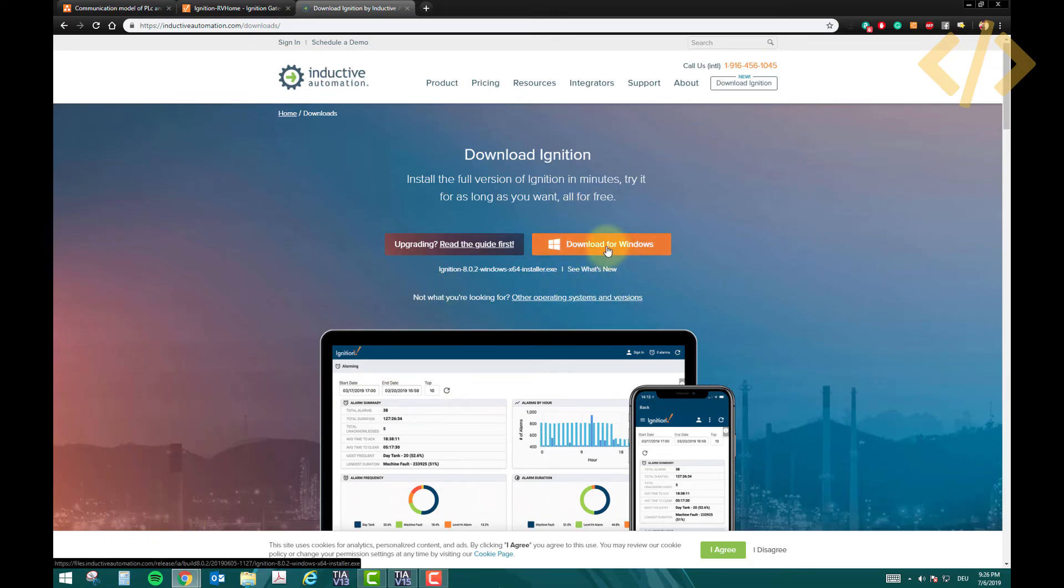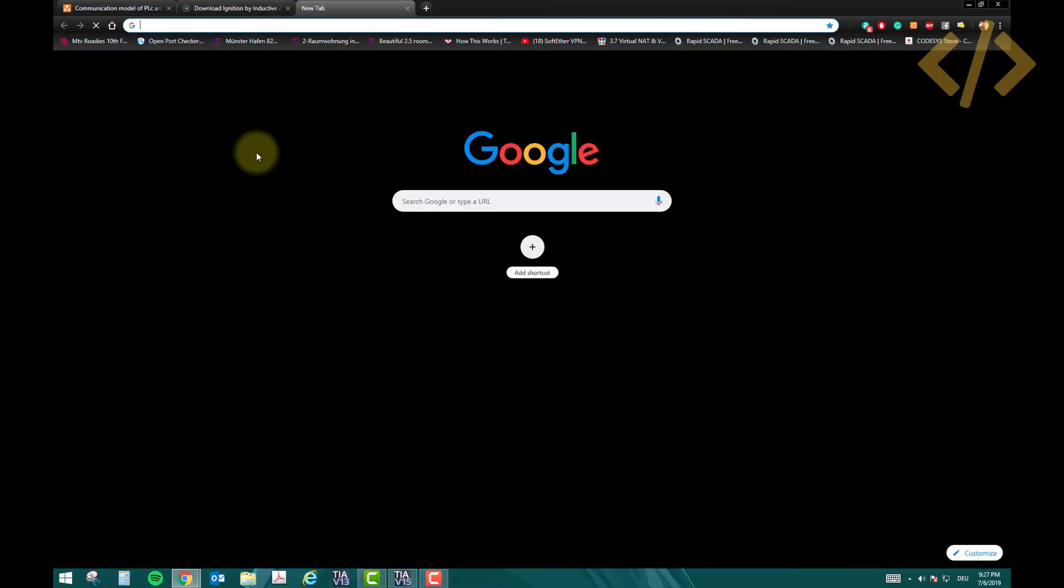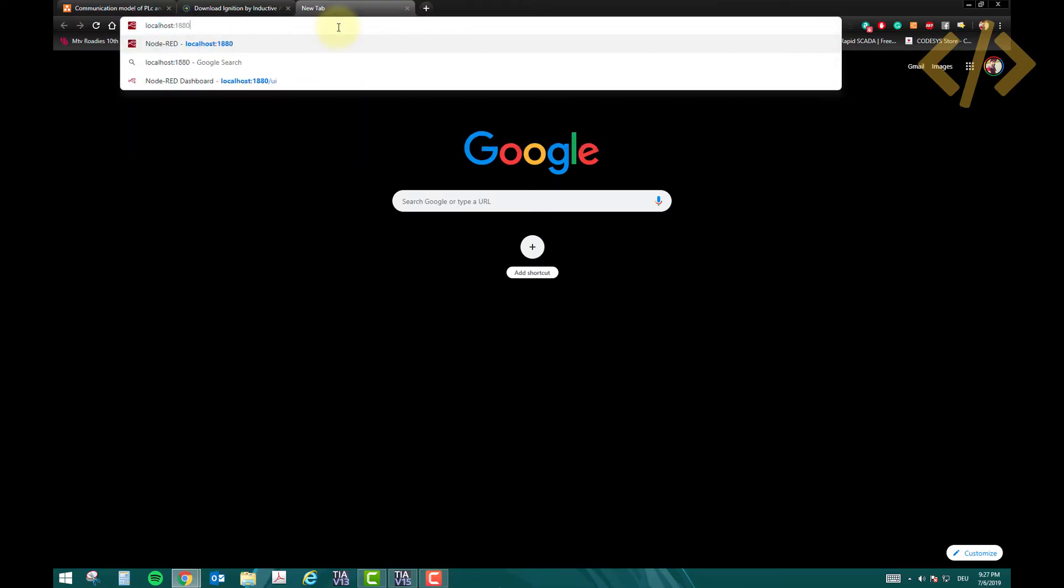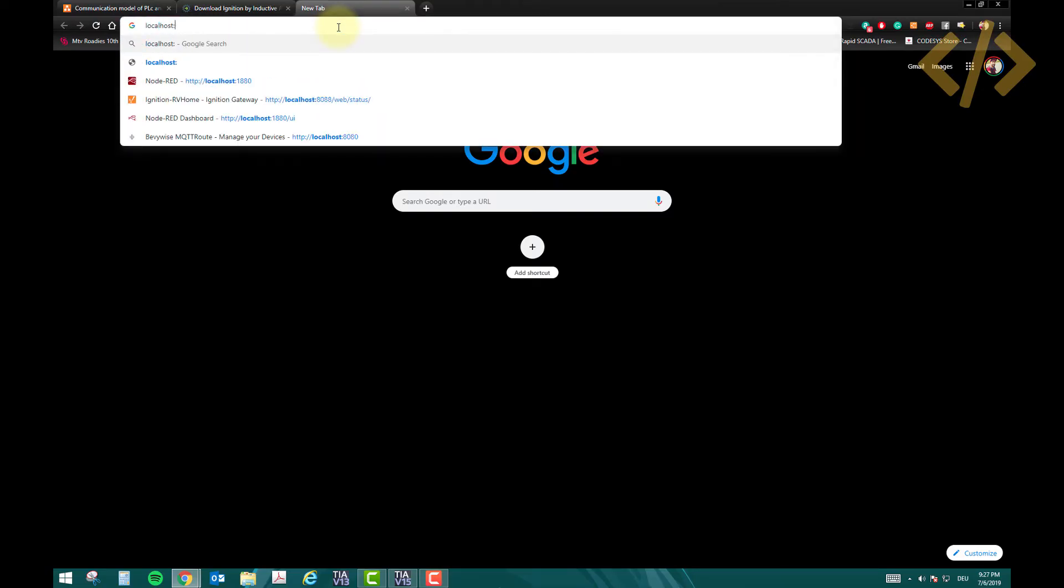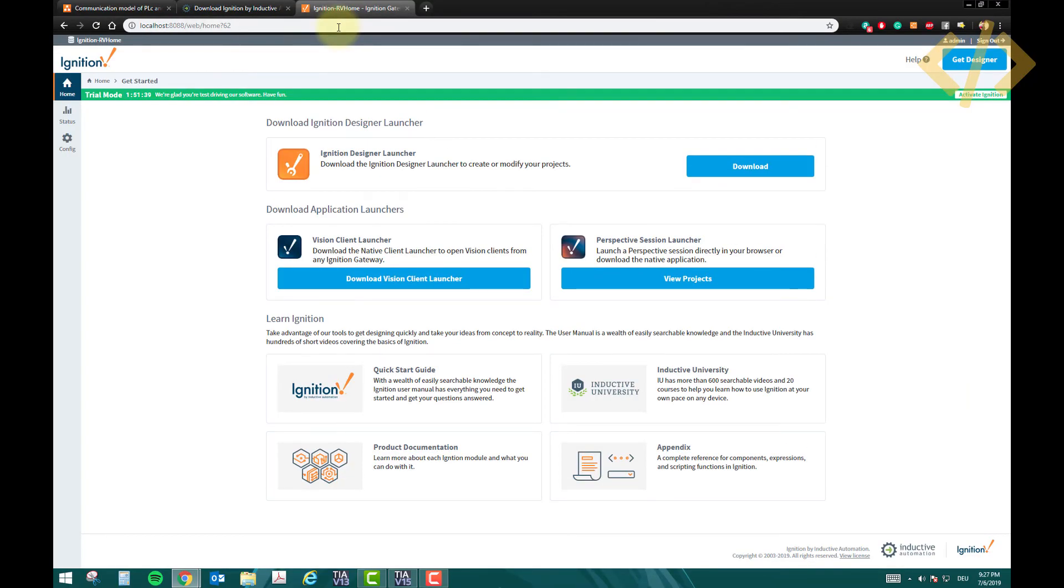Once you install the Ignition software, it's very easy - it's just an exe file, you just have to open it and it will do self-installation. Once it's completed, you have to open a new tab in your browser and type localhost and use the port 8088. This is the default port of Ignition. When I enter this, I will come to this main screen.